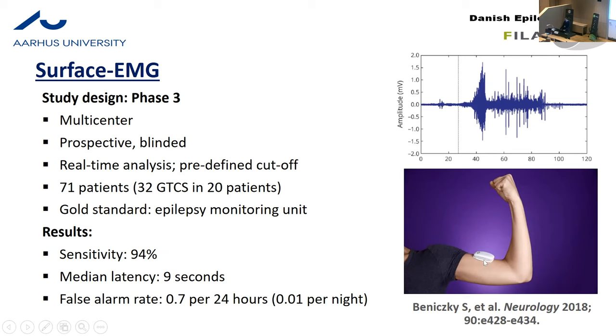This is the mini EMG — a plaster which contains the EMG electrodes, and this is the signal from this device. A phase three study is a multi-center prospective blinded study with real time analysis, with a clear gold standard from epilepsy monitoring units. The sensitivity of this gadget to catch a generalized tonic-clonic seizure was 94%, with a good median detection latency of nine seconds and a relatively low false alarm rate, especially during the night.